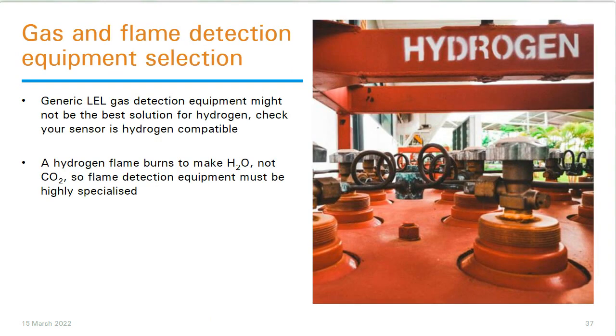And when we think about gas detection, we need to think about the sensors that are going to be appropriate. When we think about flame detection for hydrogen, we really need to check that any existing systems that we have in place will be appropriate, or if we're purchasing new systems, that they will be appropriate for use with hydrogen. Why is that? Well, because a hydrogen flame burns to make water, not carbon dioxide and soot and water. It just burns to make water.